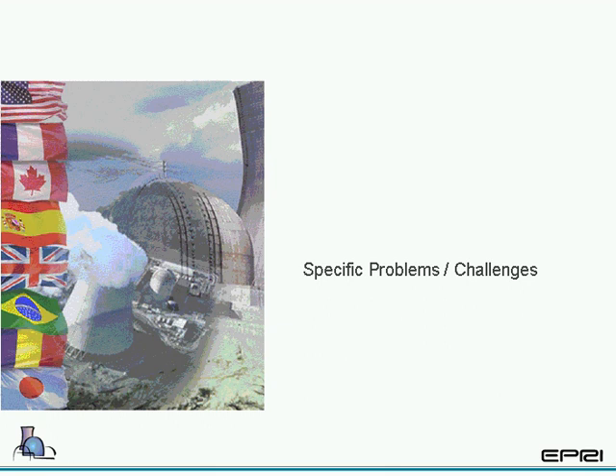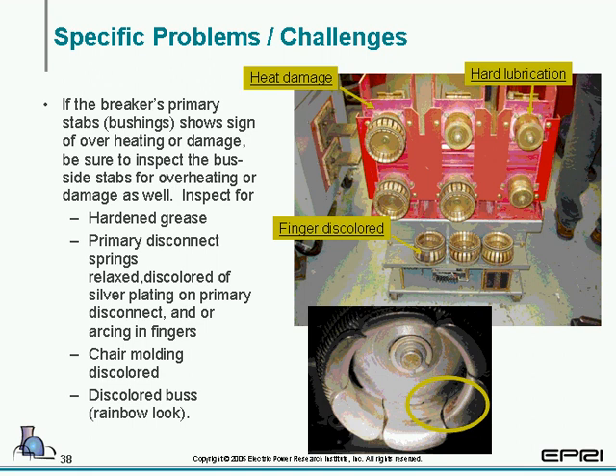We're going to start to take a look at some specific problems on the breaker that may lead to an indication that you have a problem within the switchgear itself. This particular breaker was overhauled about 4 years previous to removing it from service and finding some of these problems. Here you see it says heat damage, where it has a white discoloration around all the upper stabs and the lower stabs, where the red glastic was literally so hot that it turned that insulation white.